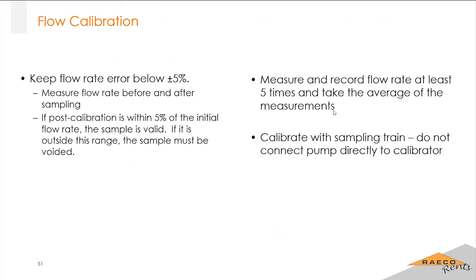And again, kind of like I mentioned before, using that Defender, you definitely want to record that flow rate at least 5 times and take the average of those measurements. So that's where the Defender comes really in handy, because it's constantly providing different measurements, whereas the 4146 is really just a number on the screen that's changing. So you're not really taking multiple measurements, just kind of holding that number.